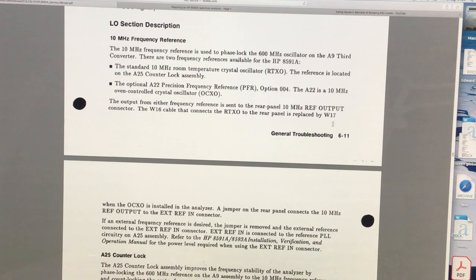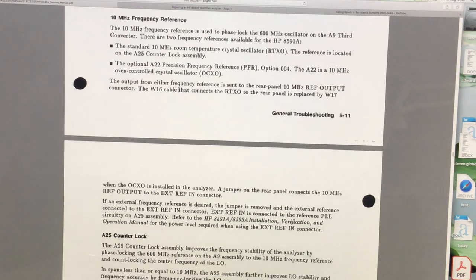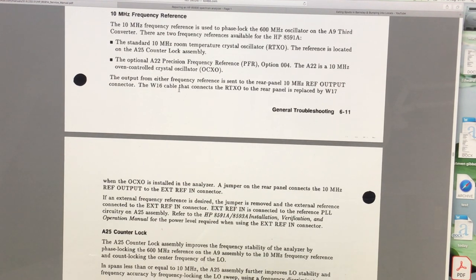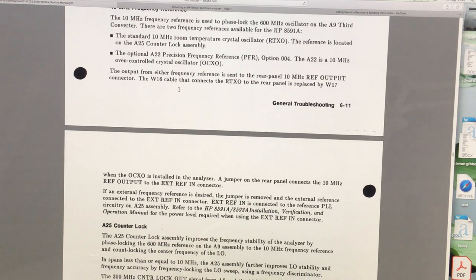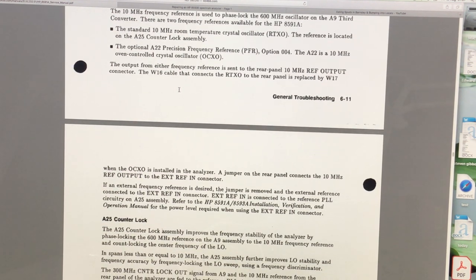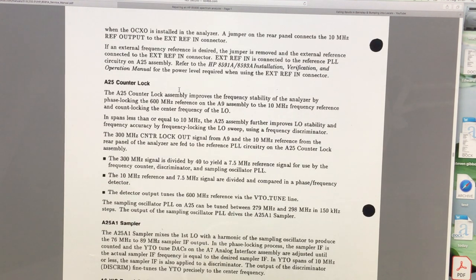Just looking a bit further into this, it says the 10 megahertz reference is used to phase lock the 600 megahertz oscillator on the A9 third converter. There are two frequency references available, and it talks about a standard one, which is what we have, or obviously then there's the optional precision one, which is option 4. The output from either frequency reference is fed to the rear panel 10 MHz reference output. The W16 cable that connects to the RTXO rear panel is replaced by W17. More useless information. When the RTXO is installed, the analyzer, the jumper, rear panel, blah, blah, blah.